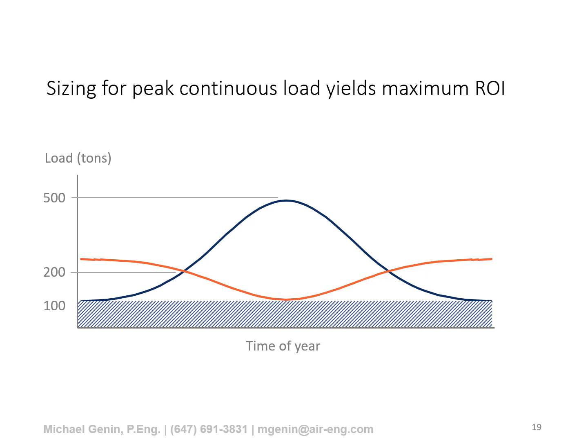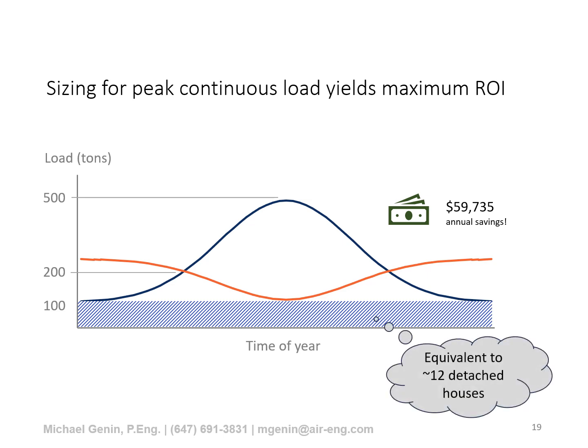And in this example, that chiller would run 24/7 to get you the most cost-efficient solution, and that's equivalent to almost $60,000 annual savings, which is fantastic for a 100-ton machine. And put in perspective, it's equivalent to the peak heating load of about 12 detached houses that would be removed completely from the system. So again, heat recovery can have a tremendous impact when we're talking about decarbonization.